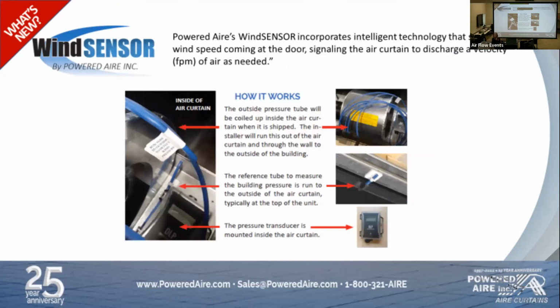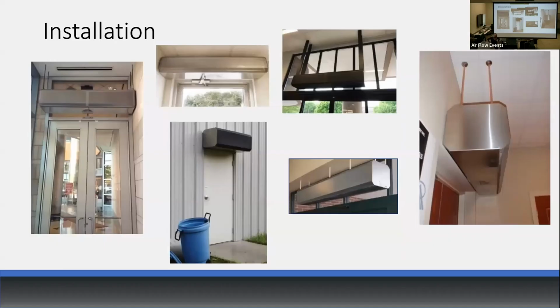It's wind sensor technology. We have EC motors that are variable speed, so we can now give you an air curtain where the speed will be dependent upon the wind velocity outside. The windier it is outside, the higher the speed of the air curtain. If it's a calmer day, the less airflow that's going to come out of that air curtain. So is there some kind of a pressure thing outside? There's a little wind sensor tube that would need to go through the wall that would sense that, and it ties into the air curtain. Yep.